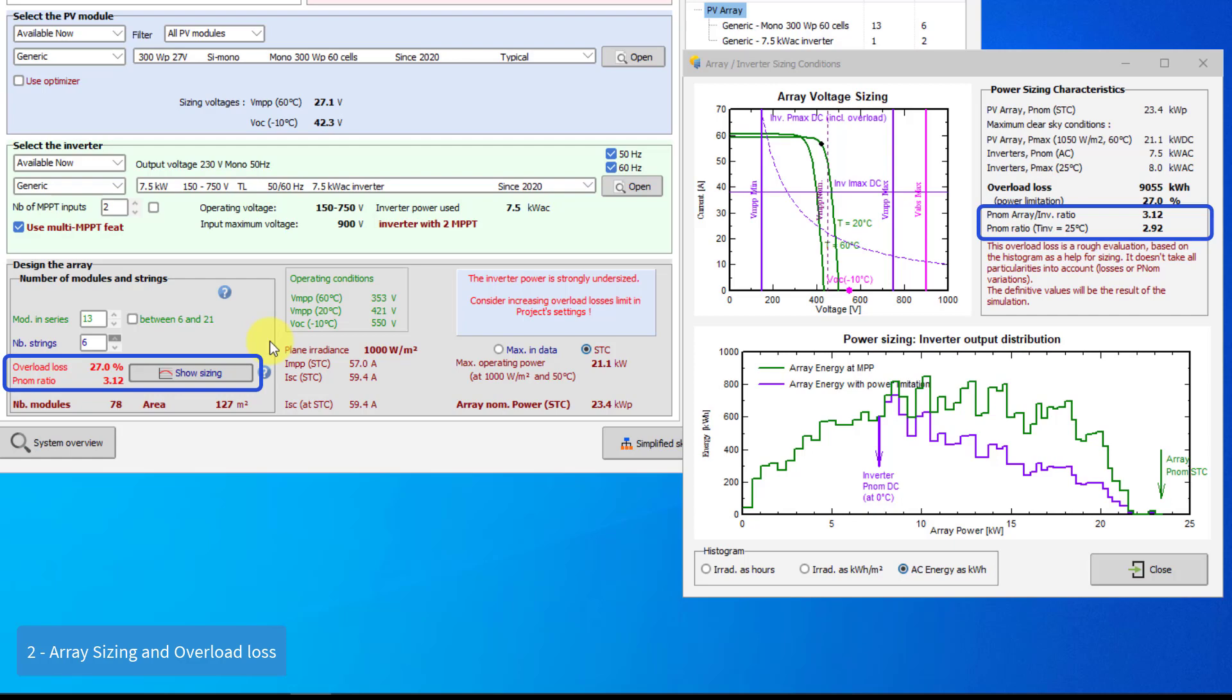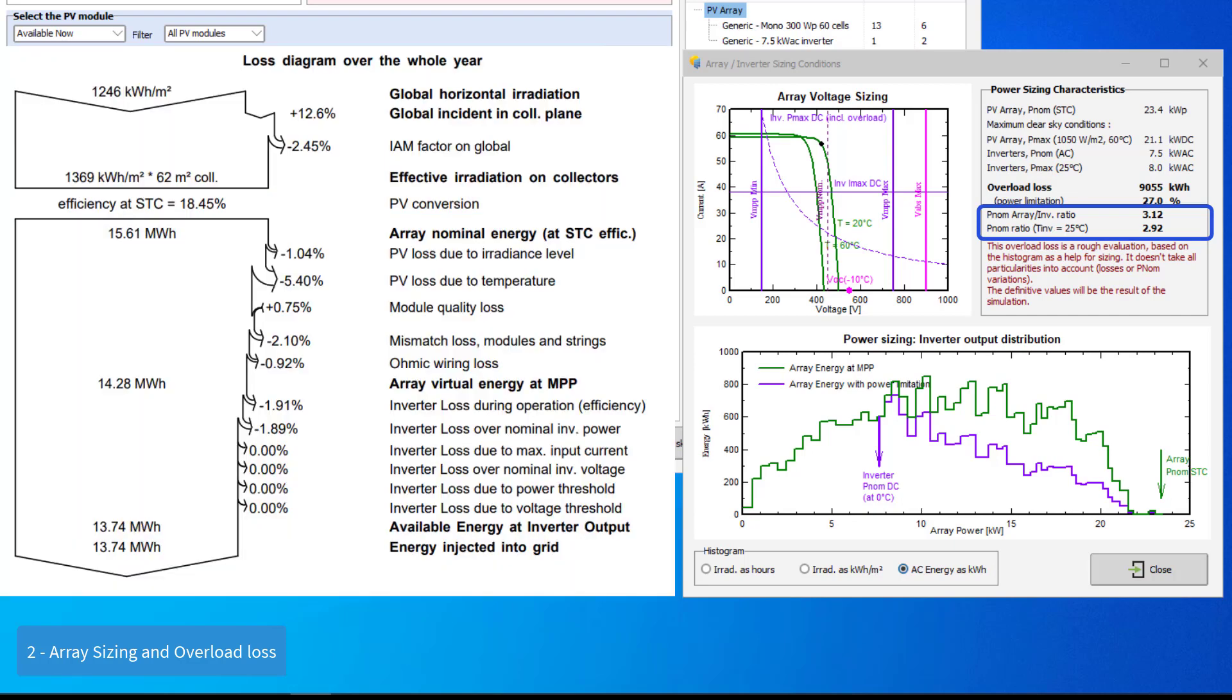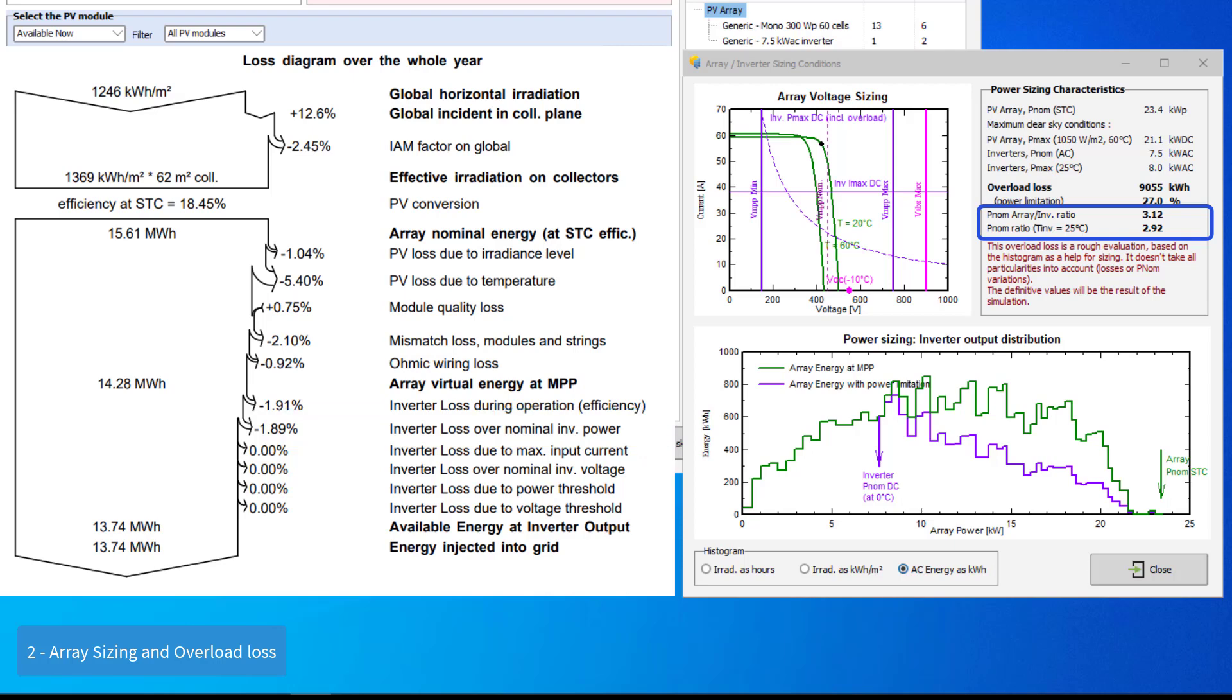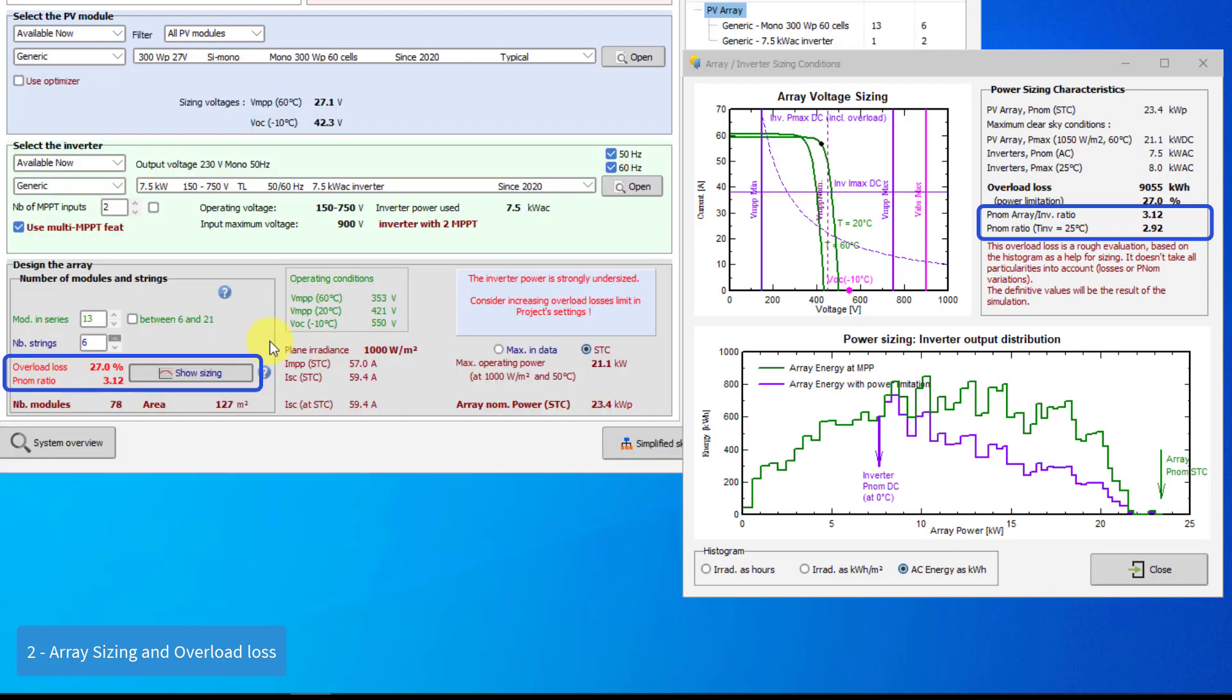Note that the overload loss calculated by the simulation may be significantly different from this sizing value. This is because the calculation of the histogram for this rough sizing tool cannot take all the system losses into account. The reference result will of course be the result to the detailed hourly simulation.